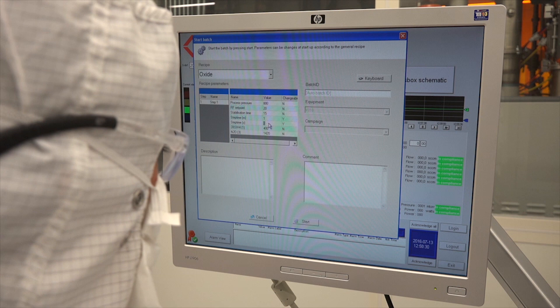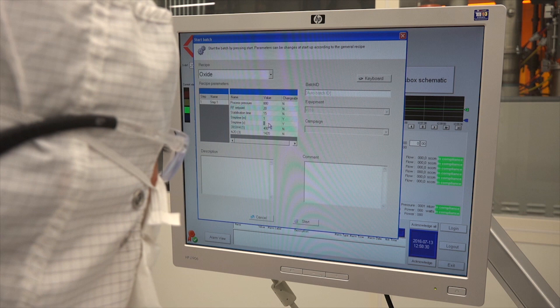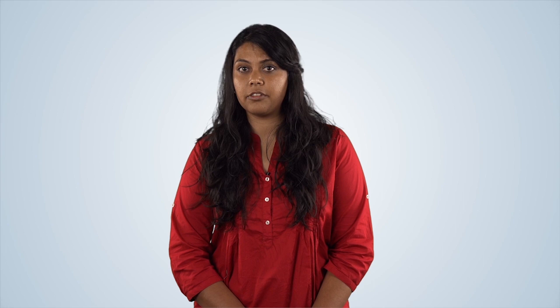We are now ready to begin the PECVD deposition by clicking Start on the computer. When we click Start, the gases begin to flow and the pressure rises to a preset value defined in the recipe. When the pressure stabilizes, the RF power is turned on, which starts the plasma.